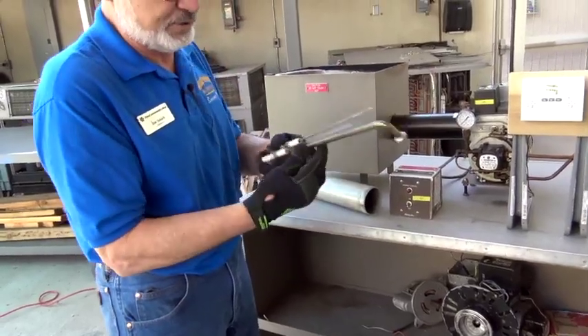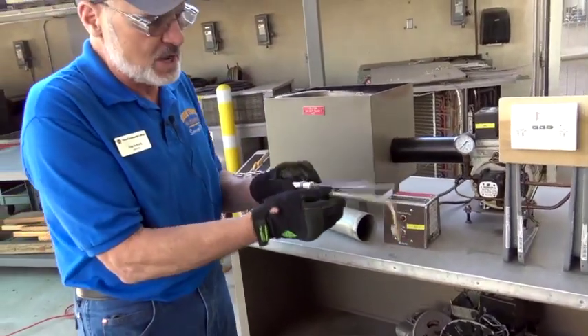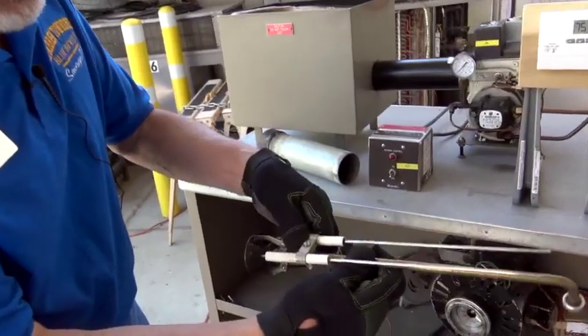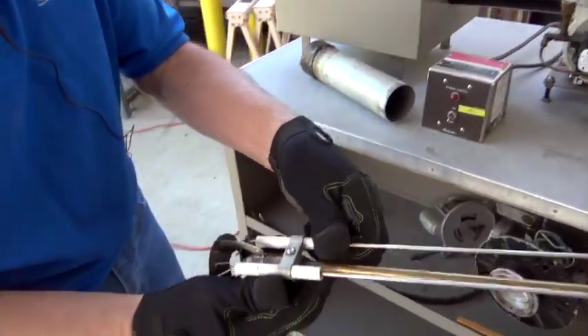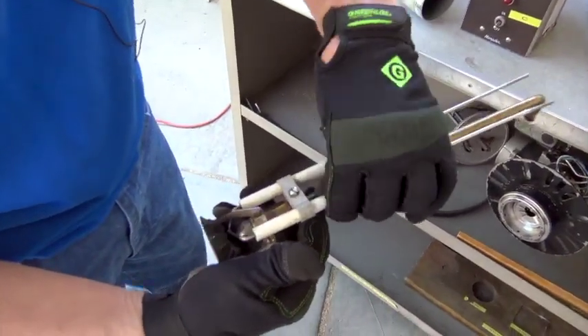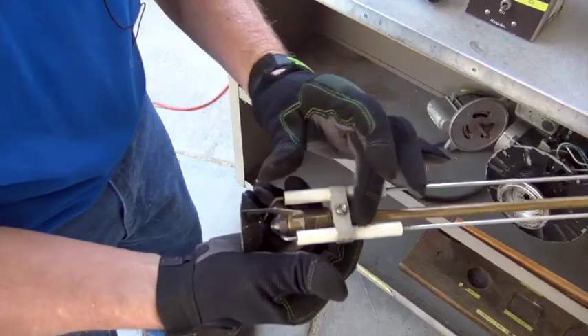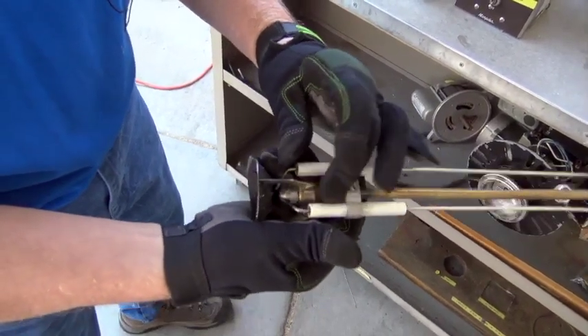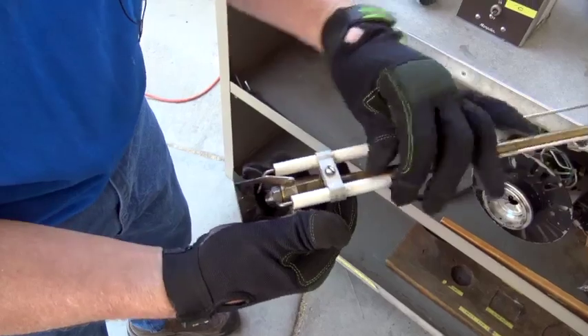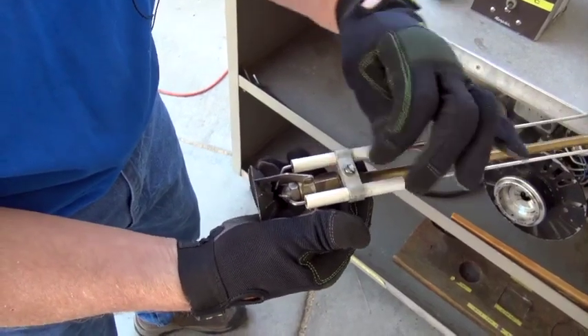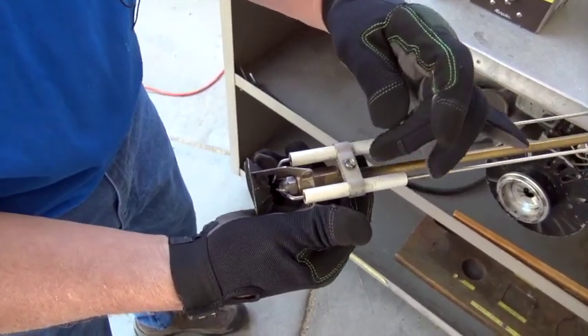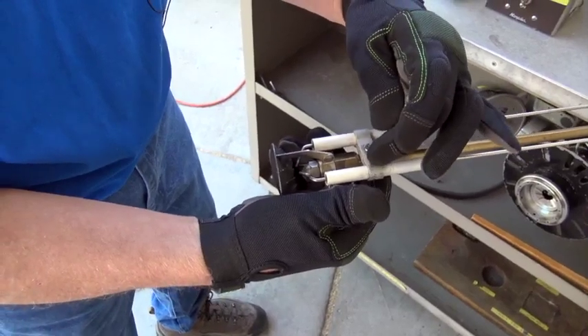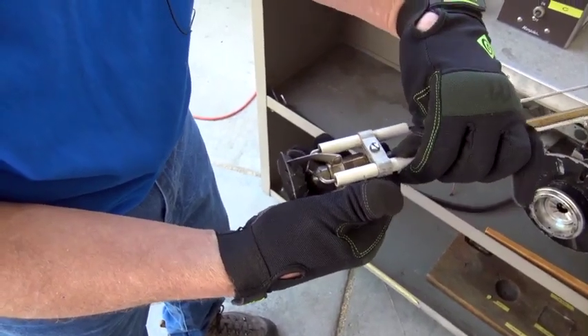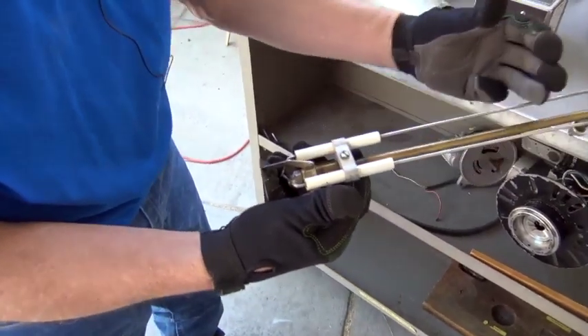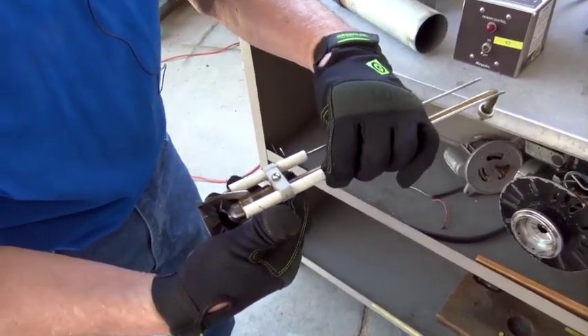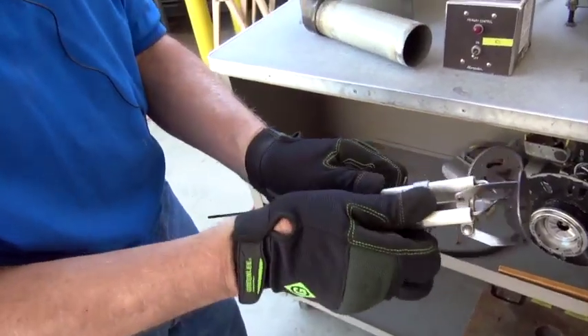This is our fuel tube assembly with our electrode assembly. As you can see, this one was bad. It was worn out, loose. The clamps are real tight. This is porcelain. We don't want to crack this, because if you tighten it too tight, it'll crack. I've done in the field where I put spacers in there temporarily when it's real loose until I got a new electrode assembly. And you have to set the gap according to the book.